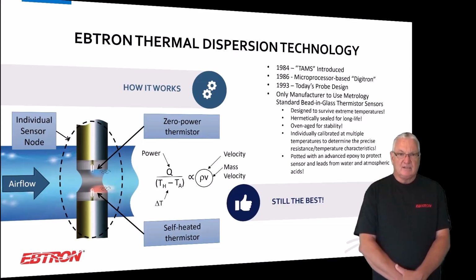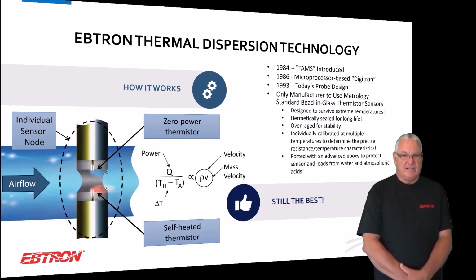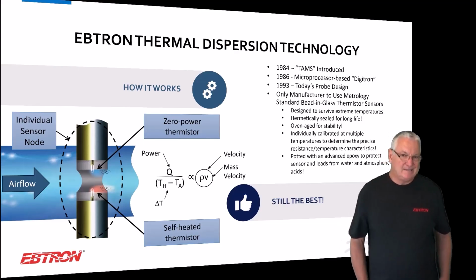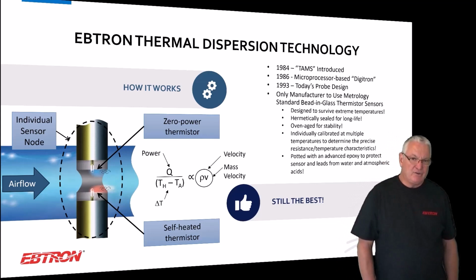And so when you look at that little relationship near the middle of the screen, from your perspective, I think this is all you really need to know. If you know the power and the delta T, you have a relationship that's proportional to the velocity or the mass velocity. So that's how a thermal device works. That's how ours works. There's people that do it differently than we do it, but this is how we've done it for the last 40 years.